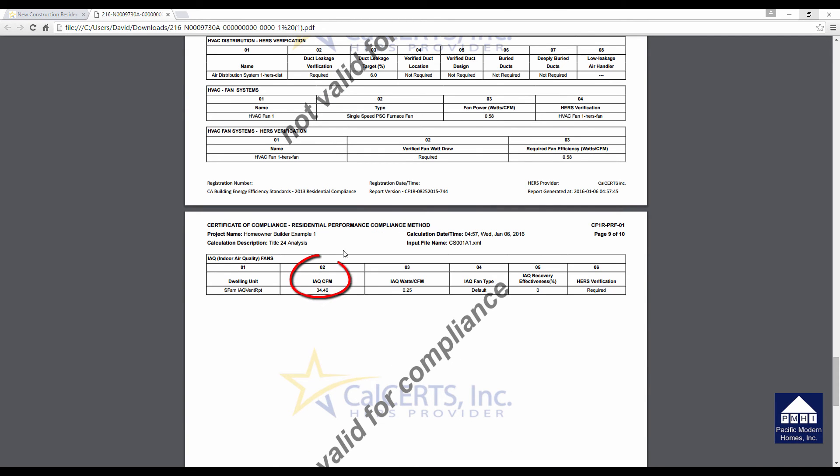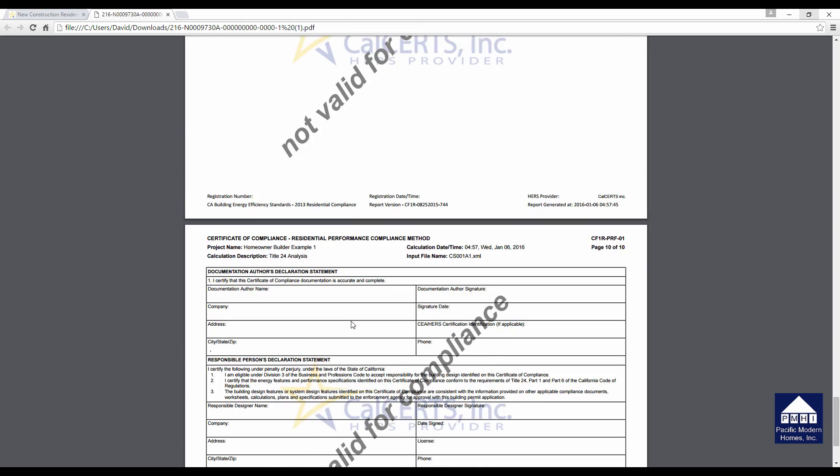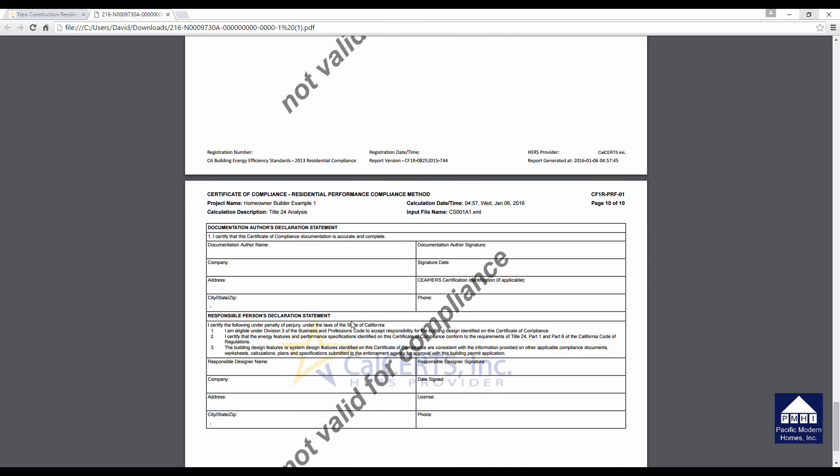The indoor air quality says that your indoor air quality fan, which is typically a bathroom fan, has to provide at least 34.46 CFM. The HERS Rater will be in to check that. But when you do use a bathroom fan to meet this requirement, which is the most common approach, you want to make sure that the duct on that fan unit is straight pipe, and it's taking the shortest route possible. Otherwise, those small fans cannot provide adequate ventilation. And you'll find yourself in a position where somebody's out there testing the fan, it doesn't pass, and you're going to have to either change the fan or go back in and change the ductwork, and you're at the end of construction. So you'll want to watch that a little bit.